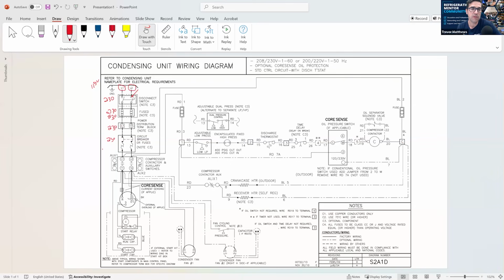They'll probably get 115, right? But if this is closed, you will get your 230 volts. Because remember, we got 115 on this one, and we got 115 on this one. So now upstream of the contactor, so L1 right here. So if we put it on the upstream side, we should get 230.